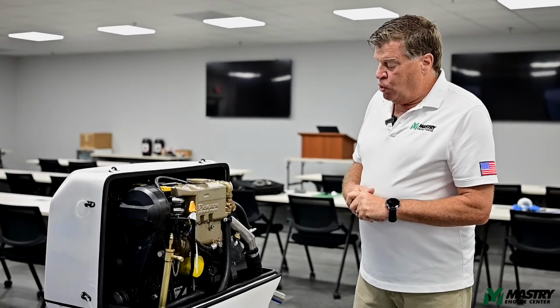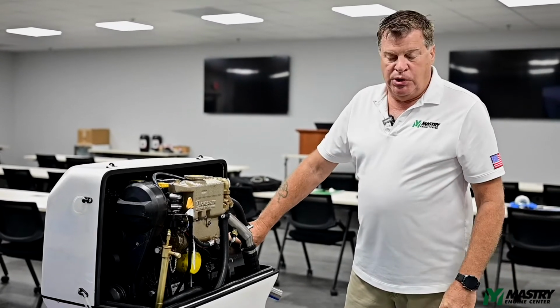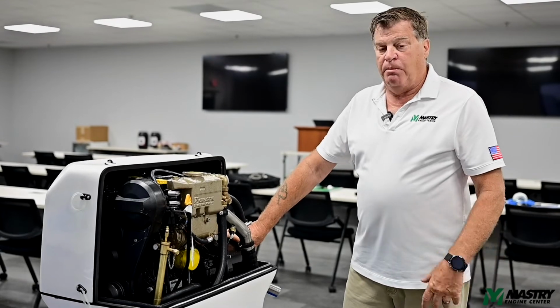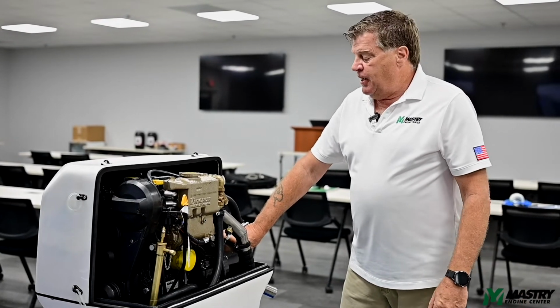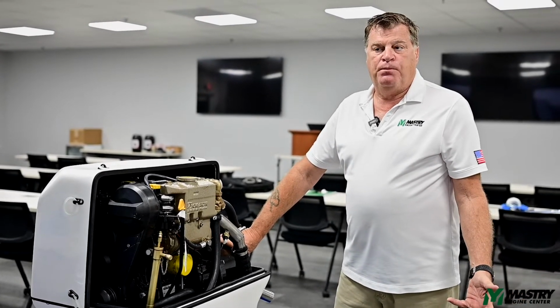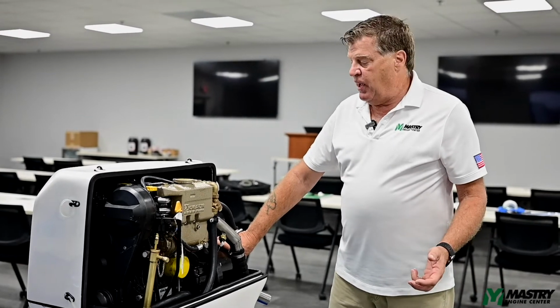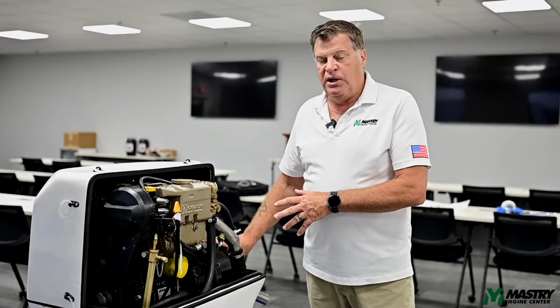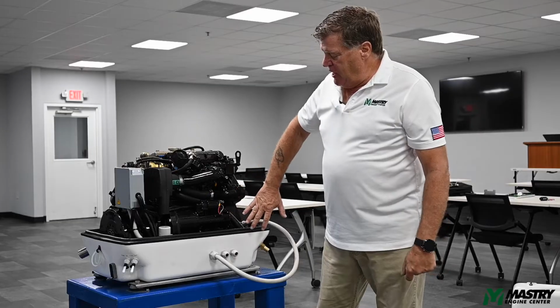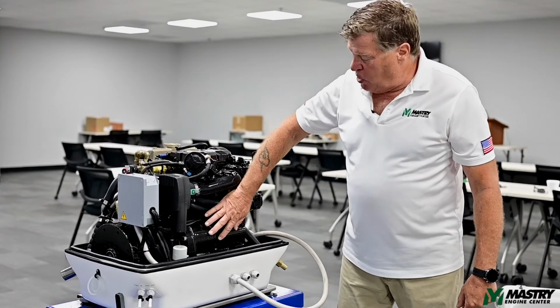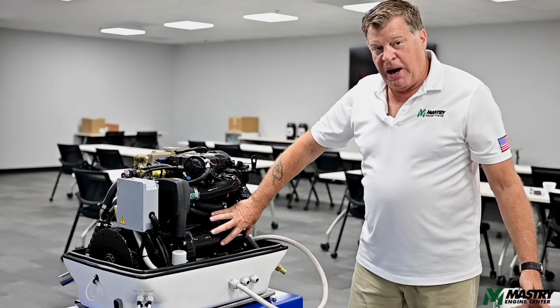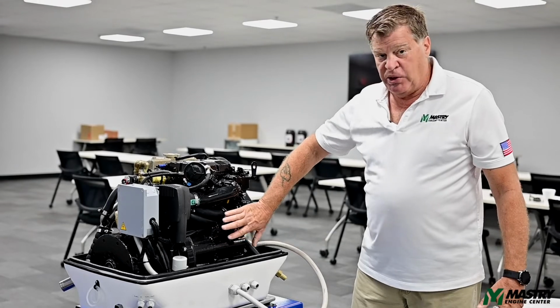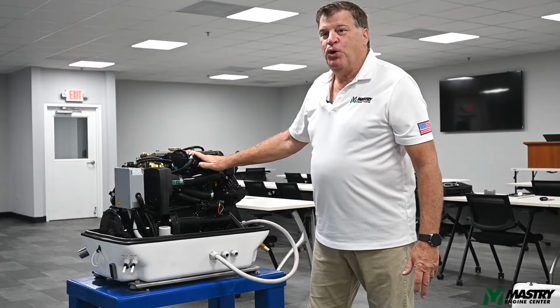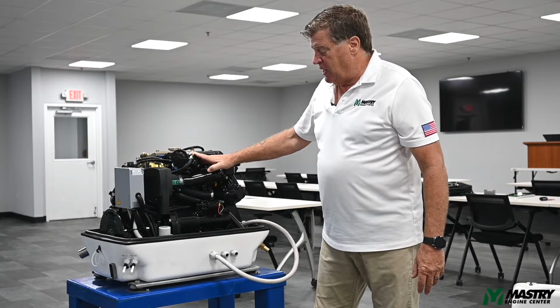The water cooling jacket on the alternator is also stainless steel. A lot of our competitors use aluminum. Some of them have air-cooled alternators, which have to have a ventilation fan. This does not require that ventilation as other units do. On this side of the engine, we have your starter motor, which is not a normal repair item, but in case there's any failures, this is where it's located. Your fuel pump is also located on this side of the engine.